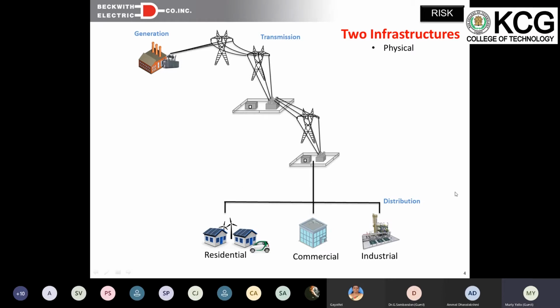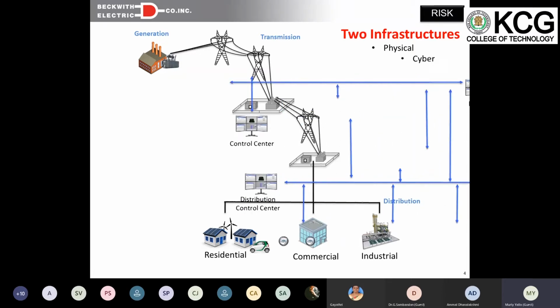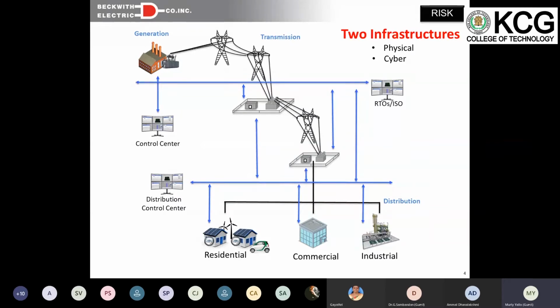Could be in India, I think 11 kV, and then it comes down to 230 volts or 400-some volts. In the US, we use mostly 120 volts in the neighborhoods, and distribution voltages anywhere from 4 kV class, 15 kV class, 22 kV class, and 34.5 kV class—these are the distribution voltages in the US. So those distribution substations get connected to residential, commercial, and industrial loads. This is the physical infrastructure that you have. Now looking at the cyber infrastructure, you've got control centers, which are controlling the power plants.